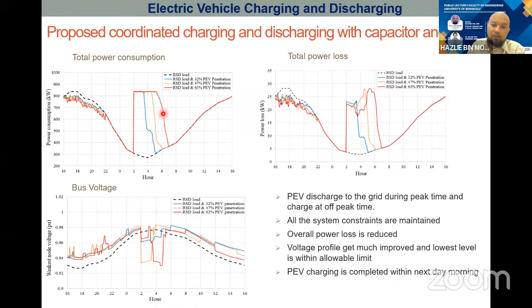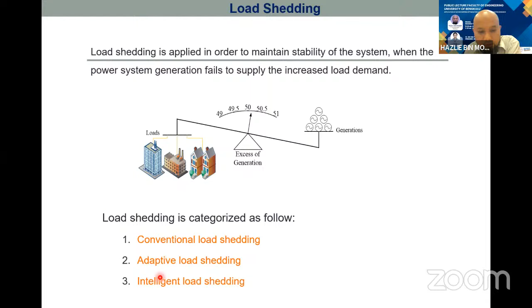If the load and generation balance, the frequency stays at the middle, 50 Hz. But most of the time, if the generation is lost or disconnected from the system, it will change the frequency. So load shedding can be categorized into conventional, adaptive, and intelligent. Let's see what load shedding is.